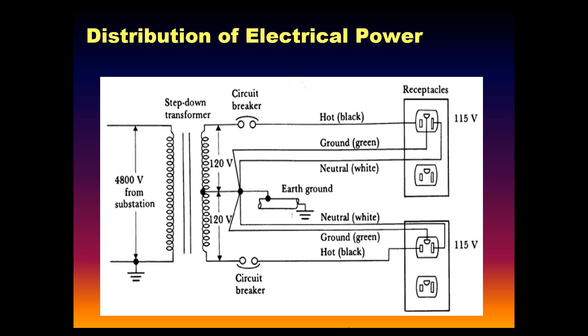So that small plate on the receptacle, the hot side, is 120 volts RMS above ground, above earth. So literally, if you're standing naked in a mud column and you stick your finger in that little hole, you're going to die. That's reference to the physical earth. There should not be any current flowing in the ground wire at all. All the current that's powering the device leaves the hot and returns via the neutral under normal conditions. But this is the crucial concept right there.